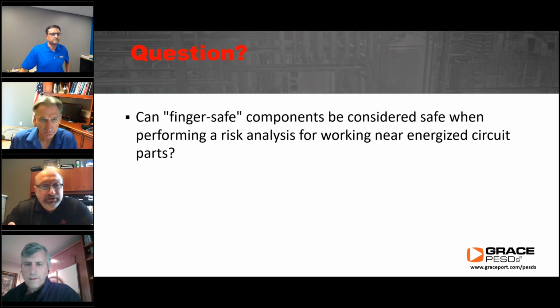So yes, if there's adequate insulation guarding and finger safe, you've eliminated the inadvertent movement risk into those conductors. And you should not receive a shock, as long as, this is another point, the condition of the finger safe guarding and insulation is still good.